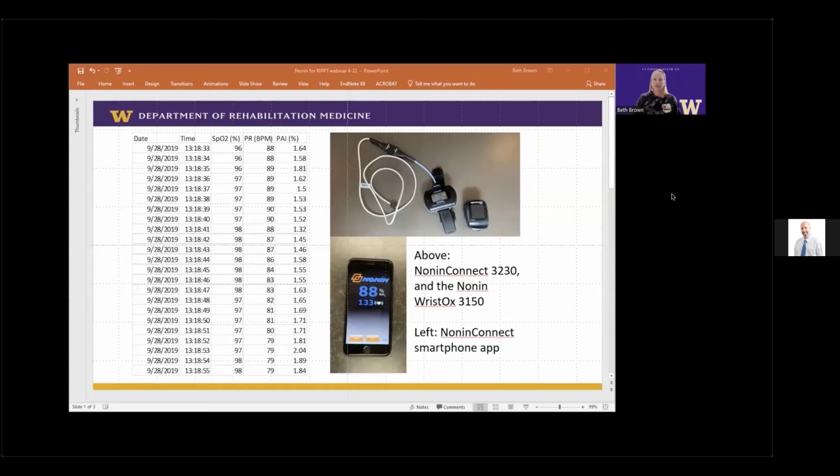This is provided by a single primary sensor, non-invasively without arterial puncture, via devices that measure transmittance of light through cutaneous tissue that has a pulsatile blood flow, like the fingertip or the earlobe, or that measures light reflectance off of cutaneous tissue, for example, at the forehead, or other locations where that's possible as well, but the forehead is most common.